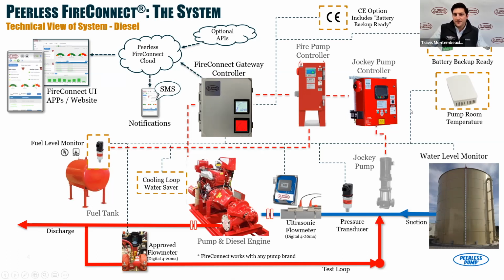What do I do?" Usually that means you got to go into the pump room and look at the controller to physically see what's going on there. But by taking that Modbus data from those fire pump controllers and outputting it to the cloud, you could actually look in the app, and we'll show you a good case study of this here in a few minutes, of what is driving that alarm. So then you can make better decisions. Do I need to rush in? Do I need to call the fire department, or can I wait till the morning? So that's an important point.